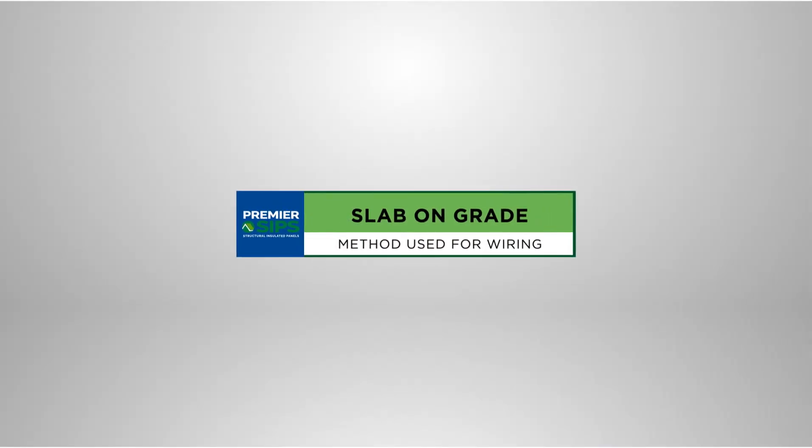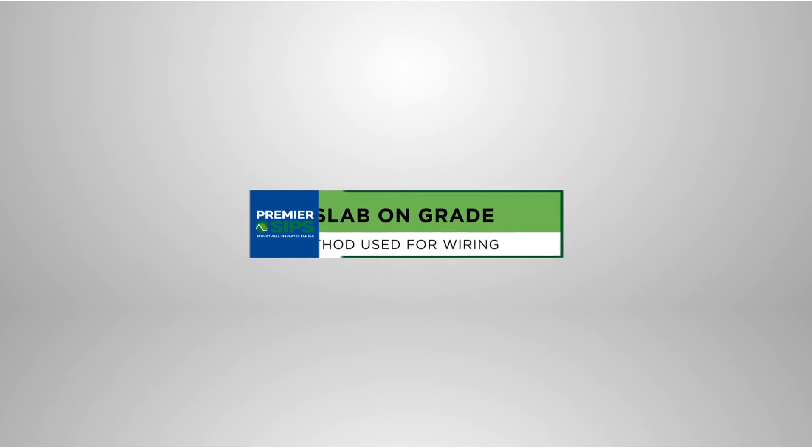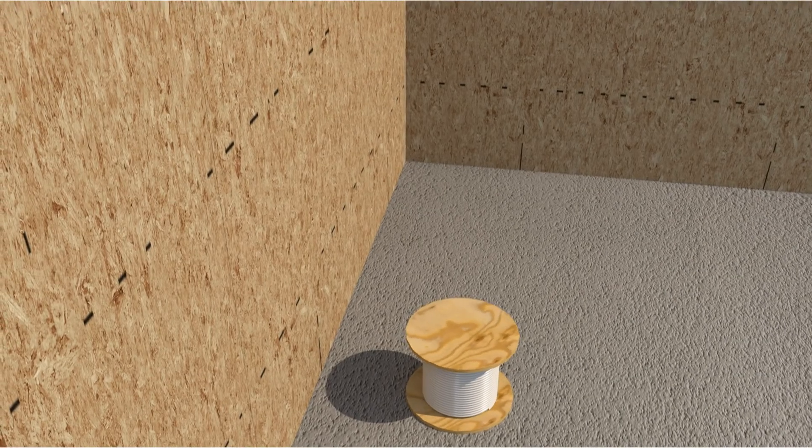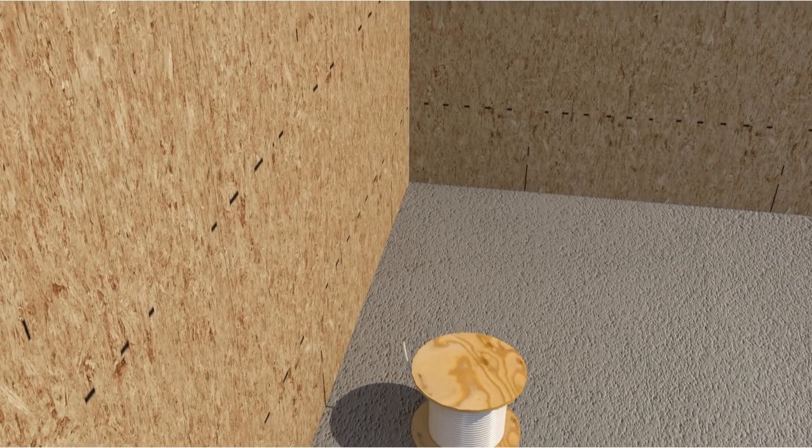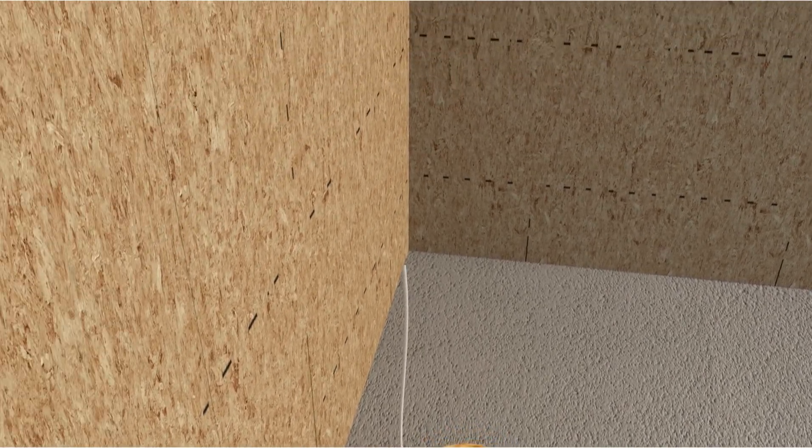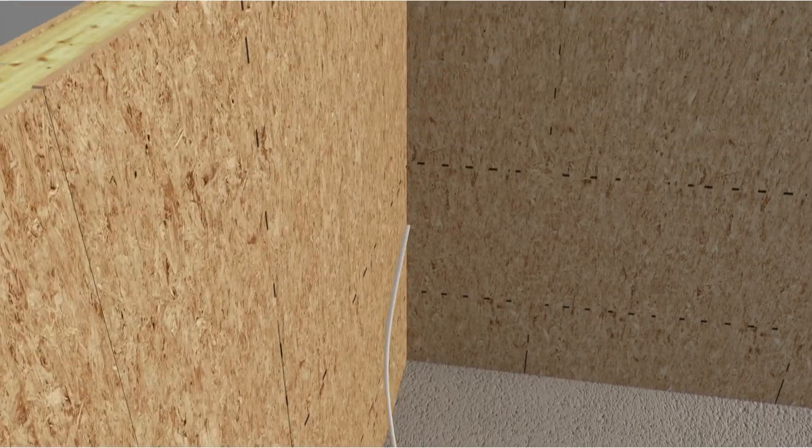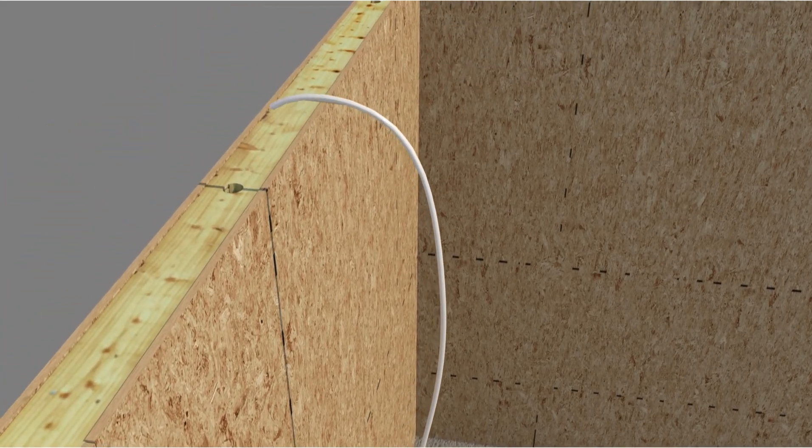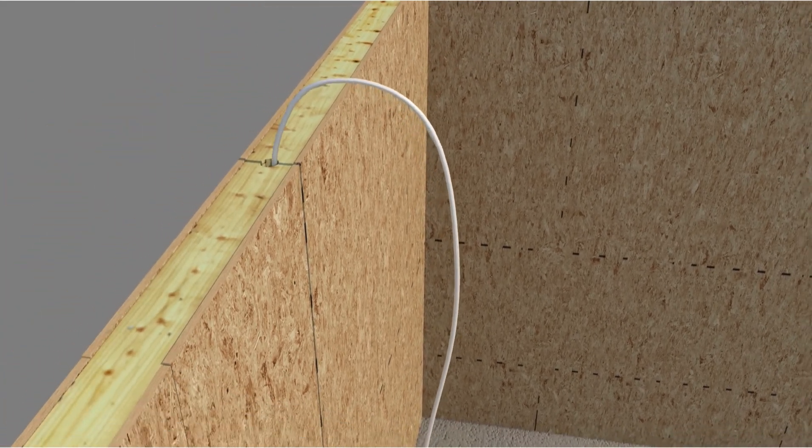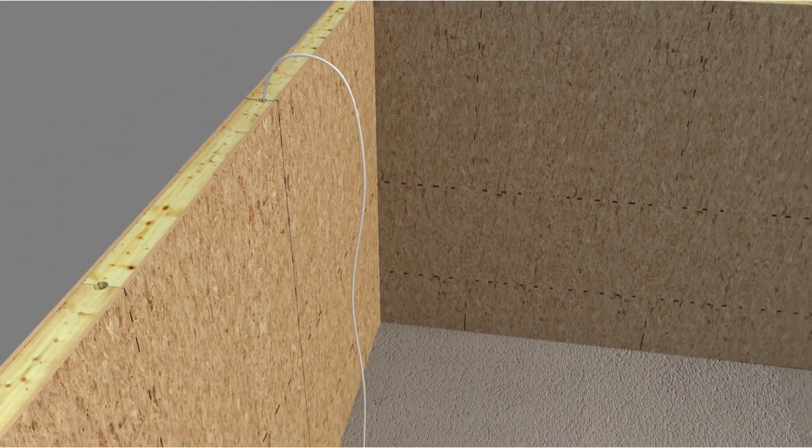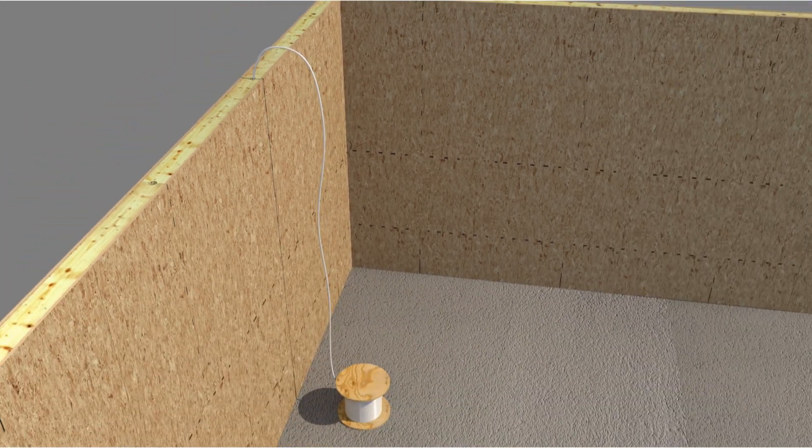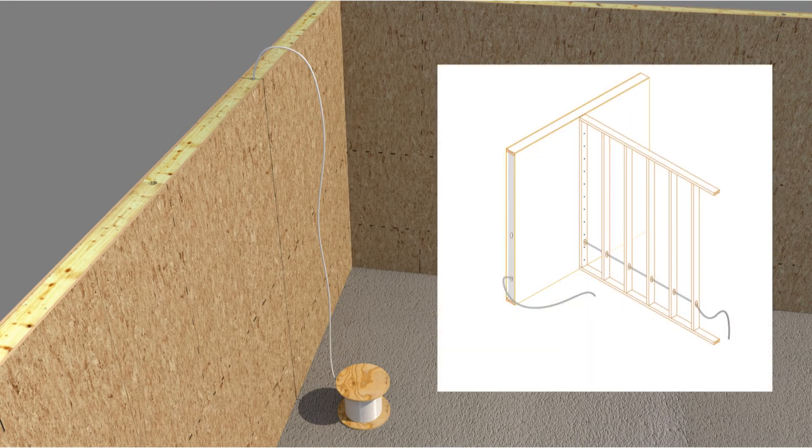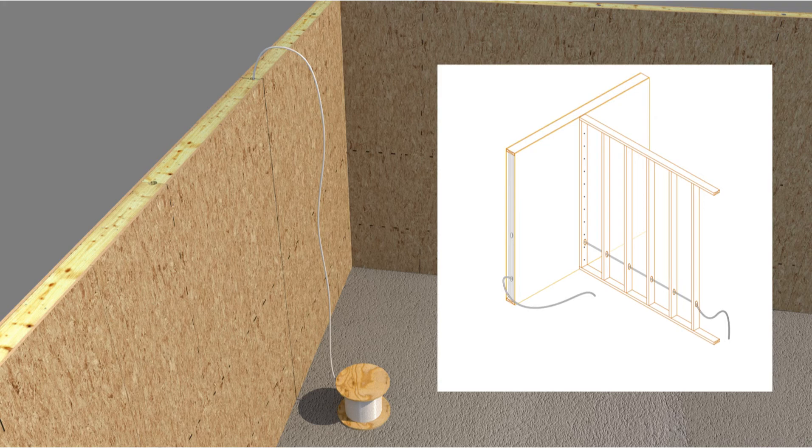Electrical wiring of SIP walls constructed over slab on grade foundations. Wiring of SIP walls constructed over slab on grade foundations is accomplished from the top of the SIP wall. Electrical wiring can now be run from the top of the SIP wall or through intersecting interior partition walls into switch, receptacle, and fixture boxes cut into the SIP walls as shown earlier in this video.